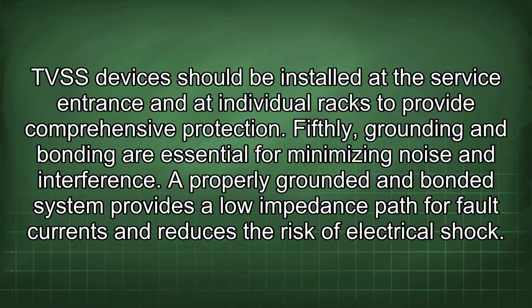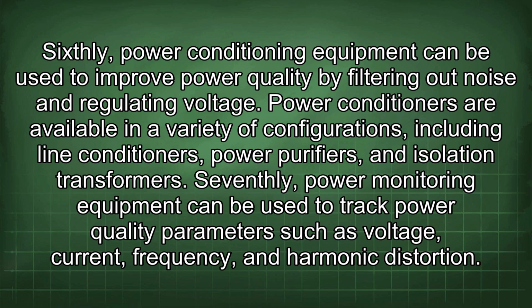Fifthly, grounding and bonding are essential for minimizing noise and interference. A properly grounded and bonded system provides a low impedance path for fault currents and reduces the risk of electrical shock. Sixthly, power conditioning equipment can be used to improve power quality by filtering out noise and regulating voltage. Power conditioners are available in a variety of configurations, including line conditioners, power purifiers, and isolation transformers.